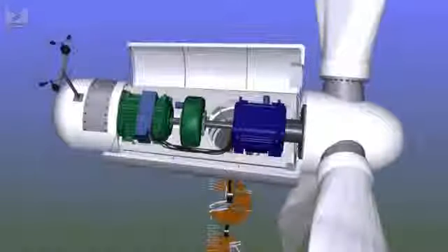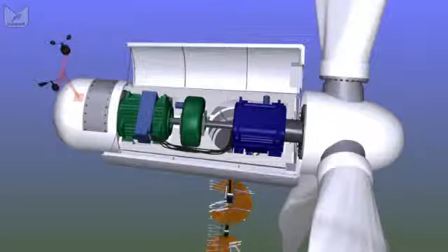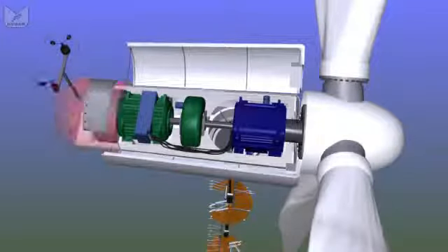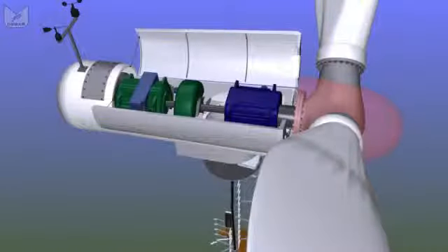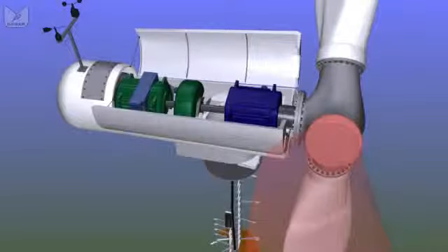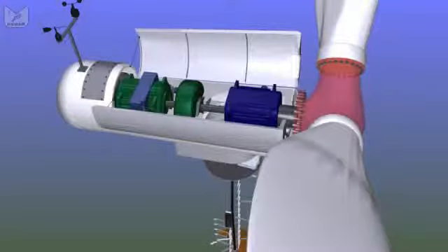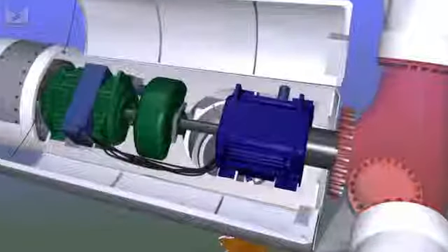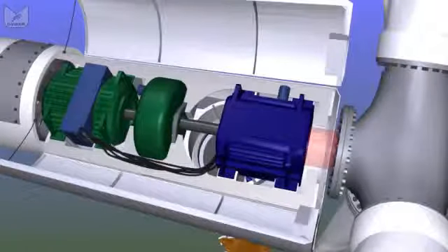And the nacelle in this case is a vaguely tapered tube. At the back we have the wind sensors, which give us speed and direction and allow the turbine to face into the wind and to change the angle of the blades. The nacelle itself is just a fiberglass tube. At the front we have a similar fiberglass cowl protecting the hub, which is a steel casting on which we have bolted our 3 blades, and the blades can turn or pitch so that the angle they form with the wind can be varied.